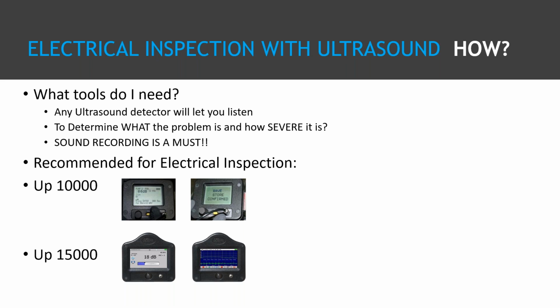So what kind of tools? Any ultrasound detector is going to let you listen. So if that's the goal, you just want to go listen to cabinets before you open them up to do infrared inspections, fine. Any ultrasound detector will do. But determining what kind of problem you have, is it corona, is it tracking, is it arcing, and determining how severe that problem is, you have to do sound recordings.